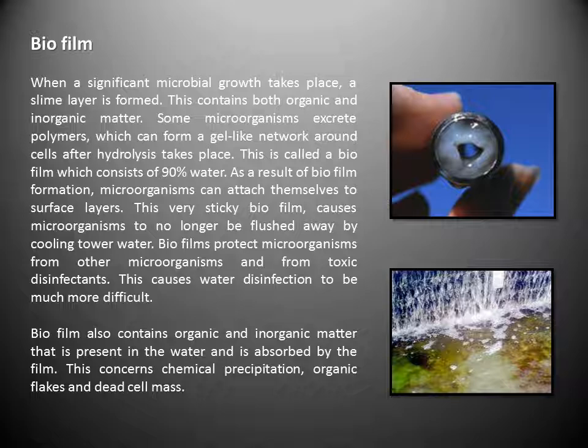As a result of this biofilm formation, microorganisms can attach themselves to surface layers. This very sticky biofilm causes microorganisms to no longer be flushed away by cooling tower water and protects microorganisms from other microorganisms and from toxic disinfectants. This causes water disinfection to be much more difficult.